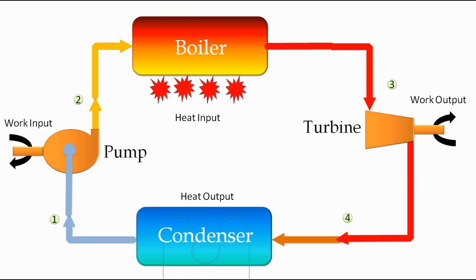Now the last component is condenser. So the steam coming out of turbine is low pressure and low temperature. So condenser again reduces its temperature and converts steam into complete water. So you may have the question, why to use condenser? Why can't we directly raise the pressure of steam and supply it to the boiler? Why convert steam into water? The answer is if we try to raise the pressure of steam, then it will be more energy consuming. Considering the mechanical output generated from this complete cycle and the work input provided to raise the pressure of steam, the cycle will not be efficient. But as compared to steam, if we try to raise the pressure of water, then the energy consumption for raising the water pressure will be very less and cycle will be efficient.